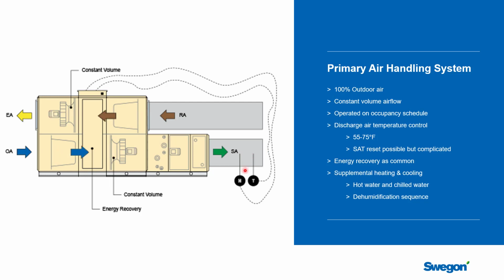And so there'll be some form of discharge air temperature sensor that will be controlling the energy recovery to maximize that, but also supplementing the energy recovery with heating and cooling. And because it's a chilled beam system and you typically have hot water and chilled water in the building, these are usually hydronic systems with chilled water and hot water coils in them to do the cooling and the dehumidification. Now, if you're going to be monitoring your humidity, which is very likely, you're also likely to have some form of humidistat in that air, and that may actually come back into the control sequence. For example, if you were doing dehumidification with reheat, you'd need to be monitoring the humidity as well as the temperature to make the right decisions about how to operate the coils.